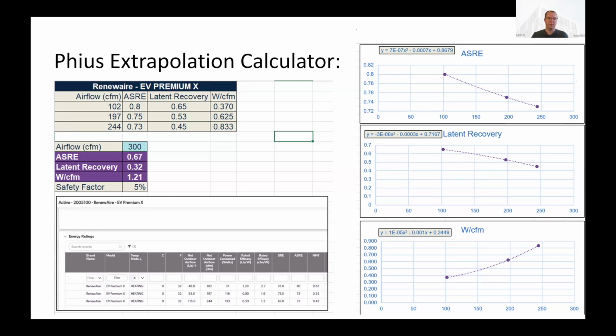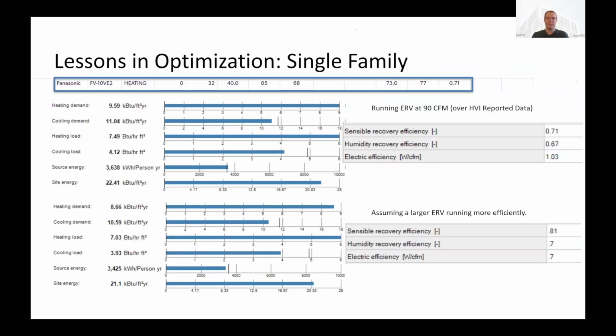So in this case, if we were running it at 300 CFM, that's beyond what HVI has published in terms of ratings. And this will calculate that curve continuing and show you what the actual effectiveness is for any CFM that you enter. So I think this is pretty cool. Like I said, I don't know that it's public yet, so maybe we're putting PHIUS on notice that they need to finish it up and make it public. But I mentioned that because that's how we got this pretty low 0.71 efficiency out of the Panasonic, because we were pushing it past the rated HVI value, right? So we have a curve that extrapolated that number for us.